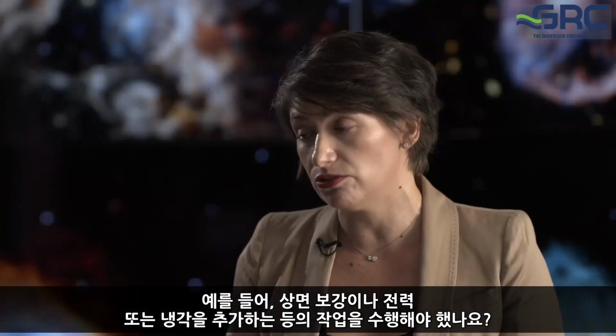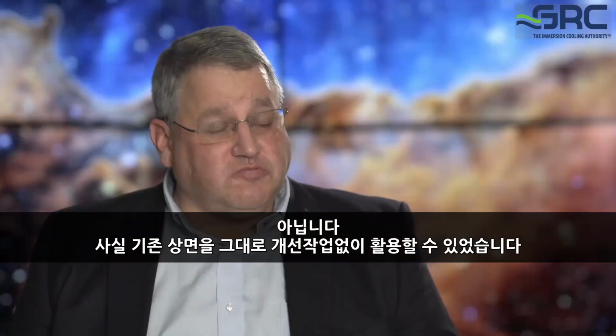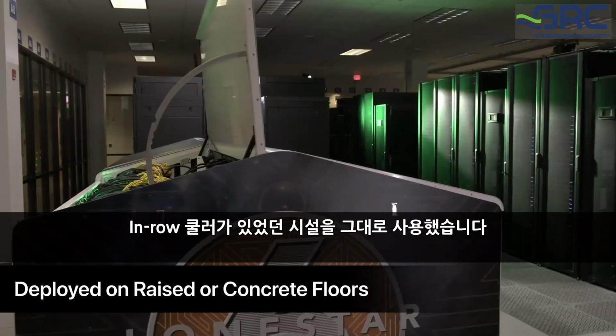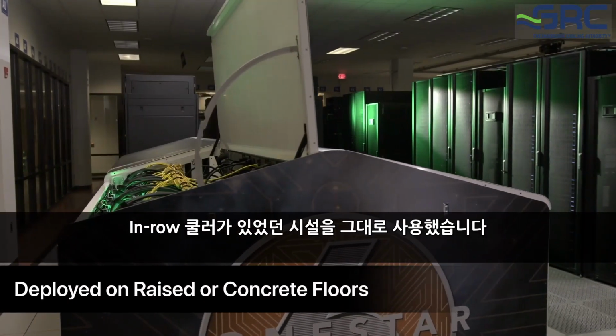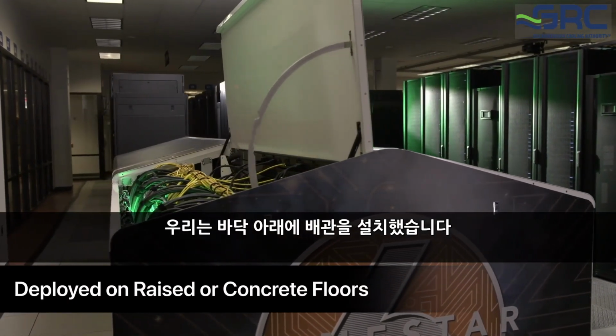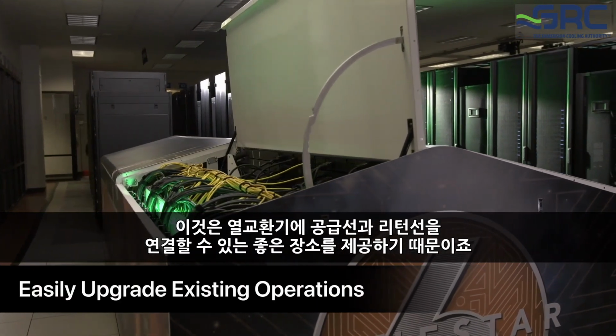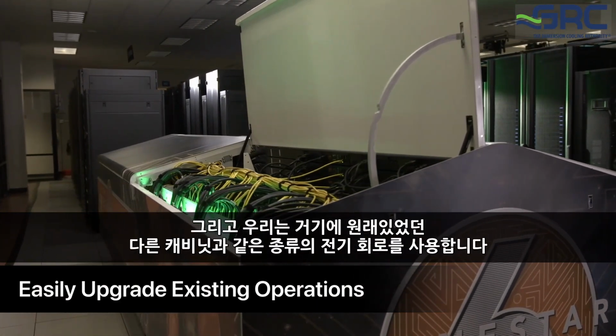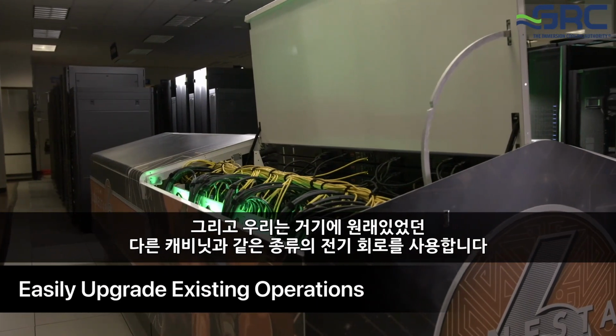Did TAC need to make any change to the existing data center infrastructure before deploying the system, such as removing or reinforcing raised floors, adding power, cooling, or so on? No, we run it on the exact same raised floor we run everything else on, because for a previous system where we had in-row coolers, we already had piping under the floor, which gives us a nice place to just hook the supply and return lines to the heat exchangers. And we're using the same kind of circuits that we had for other cabinets that were there.